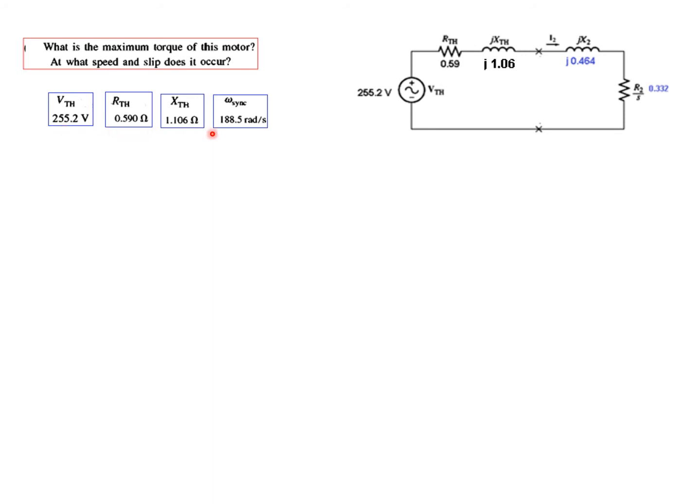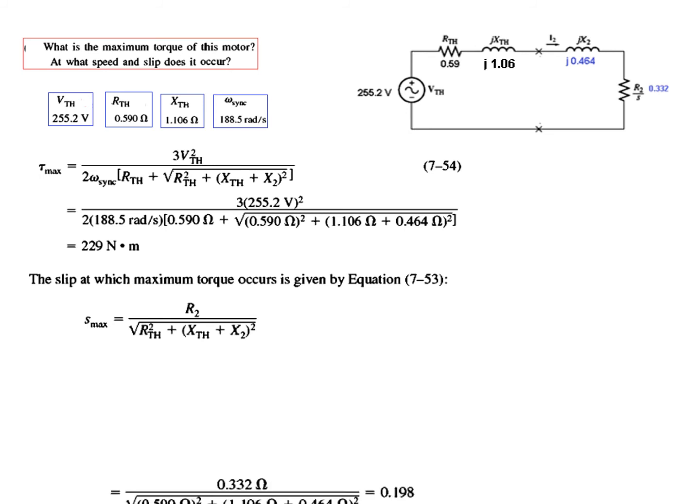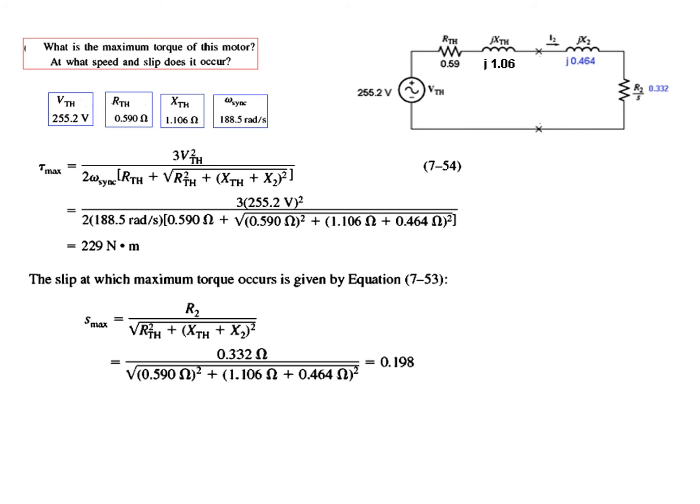Now we've found all these four terms. Let's use the formula for T_max and plug in all the values. T_max is 229 newton-meters. The slip maximum is 0.198. And the mechanical speed is 1 minus s times n_sync. We know all the values, so the rotor speed is 1444 revolutions per minute.